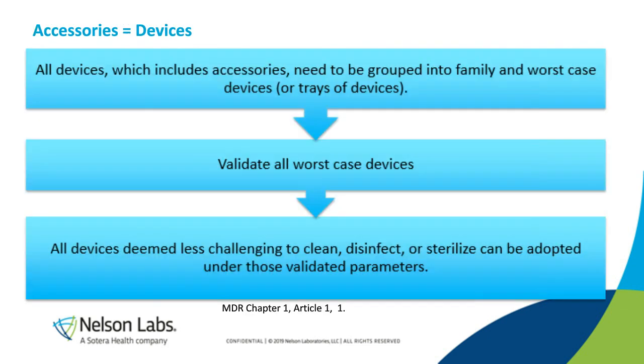When we talk about determining worst-case devices, I do want to specify, like I did earlier in the talk, that all accessories need to be included as they are considered to be devices. So when all devices and accessories have been grouped into family and worst-case devices, or even worst-case trays of devices for sterilization validations, those worst-case devices will then undergo validation testing. Then all devices deemed to be less challenging to clean, disinfect, or sterilize can be adopted under those validated parameters.